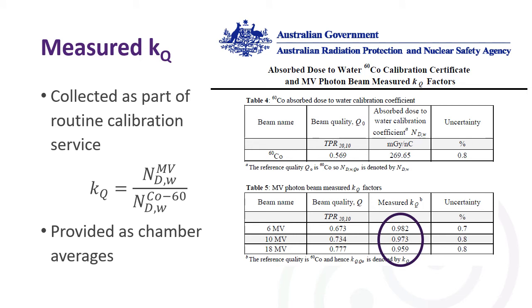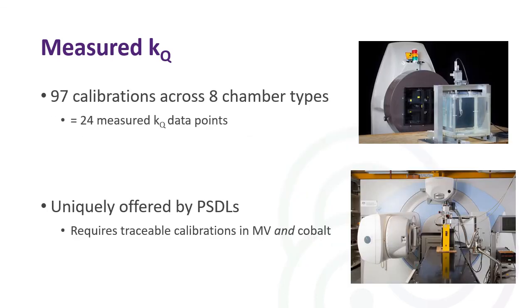The measured KQs we submitted were collected as part of our routine calibration services. The KQ in the measured sense is the NDW in MV over the NDW in Cobalt-60. You can see on the right hand side a copy of a report that will be issued, showing the three KQ values for the three ARPANSA energies. In each case we've provided these values as an average KQ measured across different chamber types. For this we submitted 97 different calibrations across eight different chamber types, giving 24 different measured KQ data points — 6, 10, and 18 MV by eight chambers — a unique service offered by primary standards dosimetry laboratories requiring traceable calibration services in both MV and Cobalt-60.